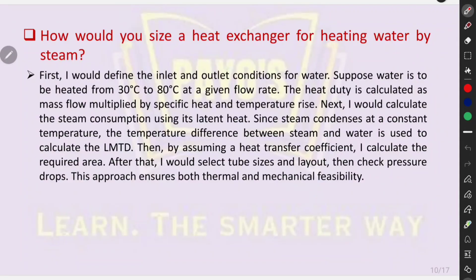Let's take a practical example. How would you size a heat exchanger for heating water by steam? First, I would define the inlet and outlet conditions for water. Suppose water is to be heated from 30°C to 80°C at a given flow rate. The heat duty is calculated as mass flow multiplied by specific heat and temperature rise. Next, I would calculate the steam consumption using its latent heat. Since steam condenses at a constant temperature, the temperature difference between steam and water is used to calculate the LMTD. Then, by assuming a heat transfer coefficient, I calculate the required area. After that, I would select tube size and layout, then check pressure drops. This approach ensures both thermal and mechanical feasibility.